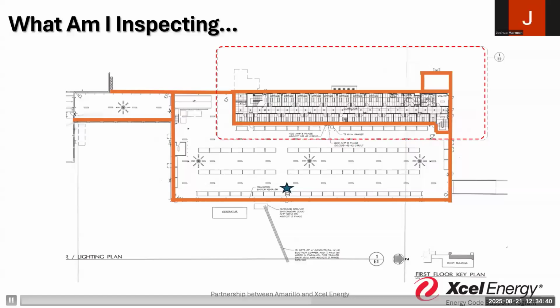What's the heating load calculation? Is it the same? No, it's not - you added 40 offices in 2 buildings. And I'm assuming, and I did, because this was the way it was designed, you lost a heating unit. So you got rid of a heating unit. I'm sure that had to affect it, right? So again, understanding where everything is, what's there, is really part of that critical assessment.